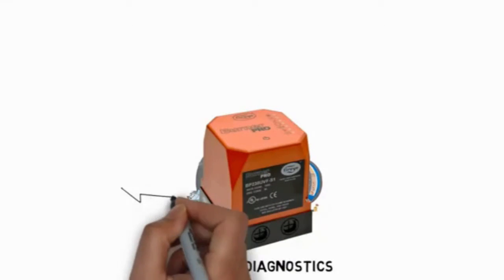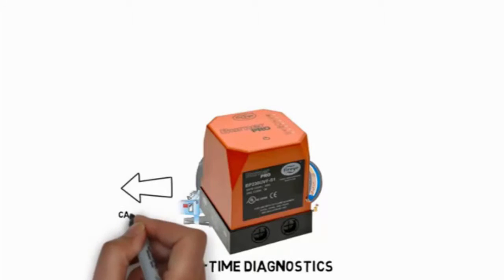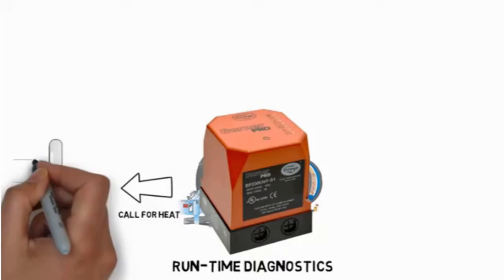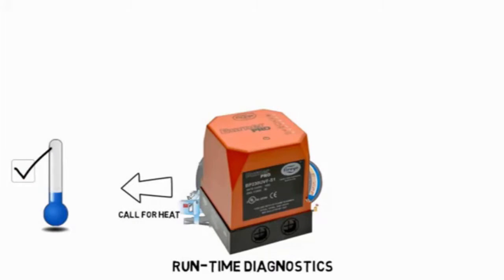Runtime diagnostics check every operating phase of the control to maintain the highest level of integrity. Upon receiving a call for heat, the system turns on the combustion air blower and commands the actuator to move to the purge position.